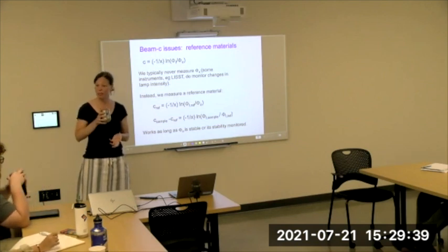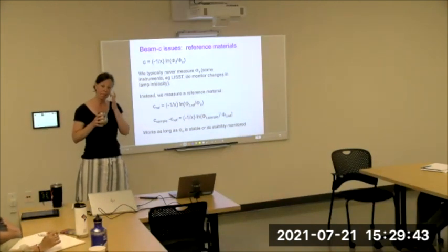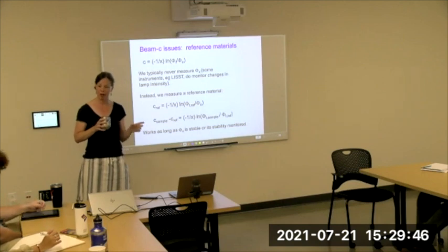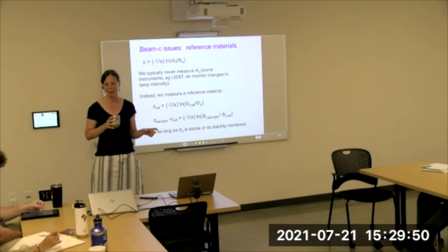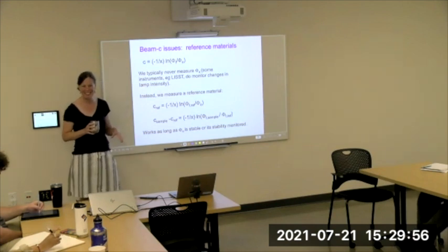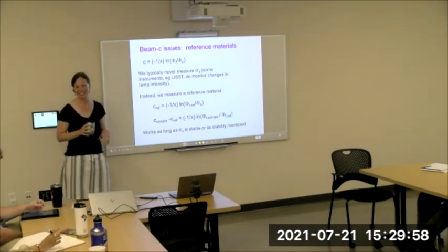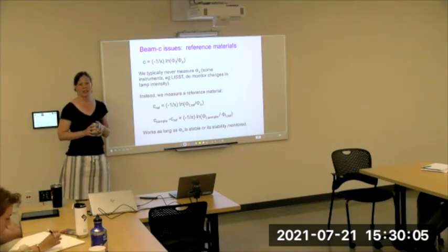You could do it relative to air. In fact, in some older studies, it was pretty common to use the air reference. It's hard to get a good stable air value on a beam transmissometer or a spectrophotometer. Yep, same issues: condensation, salt, tiny particles, aerosols. You just cover the sensor, so there's zero attenuation, so then you can see at least if the sensor had any.